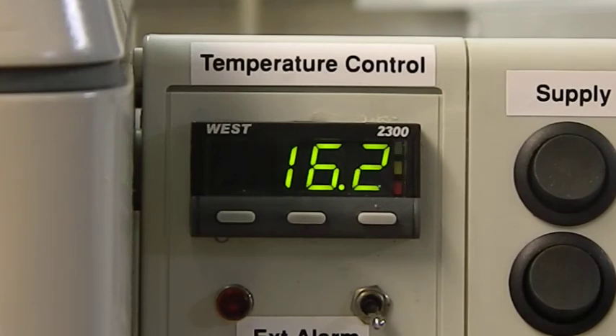The second set of parameters, which you get to by holding the right and center buttons together: SP1 37.5 or whatever operating temperature you want to be at, PB 0.5, RSET 3.40, RATE 0.35, BIAS 25, AL1 0.5, FILT 0.2, OFFS is the calibration, which we'll come to in another video, CT 2, SPL off, AEN DIS or disable.